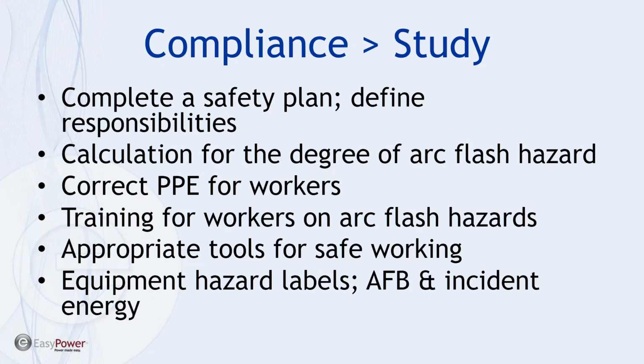Okay, the point I want to make is compliance is more than just a study. And that's one of the things you'll find when you get into the details of NFPA 70E. It requires a complete safety plan, and that's a document that defines the responsibilities for your company. Frequently, the arc flash safety plan is just part of the overall corporate safety plan, and very frequently falls into the category of electrical safety. There's also a discussion in NFPA 70E of how you calculate the incident energy, how you determine the correct PPE, the training that's required, the appropriate tools that need to be utilized, and then ultimately the labels and the boundary and making sure personnel are aware of all of that.